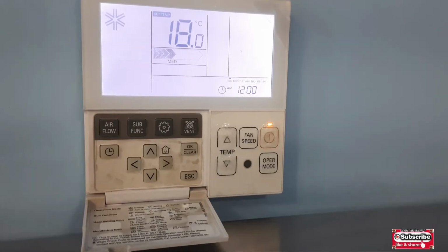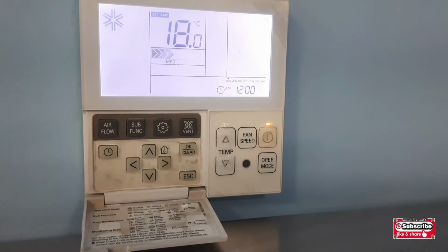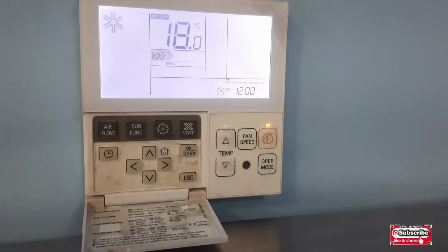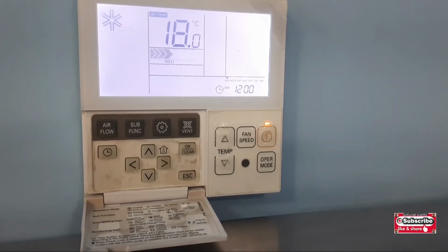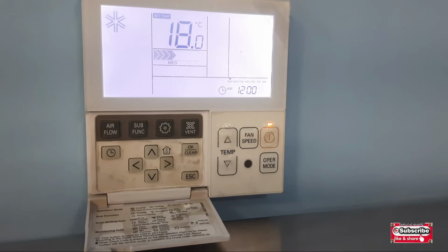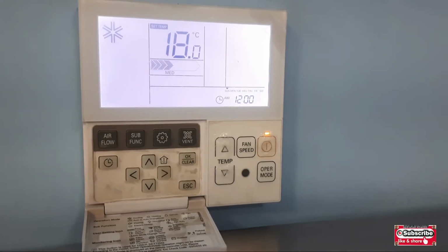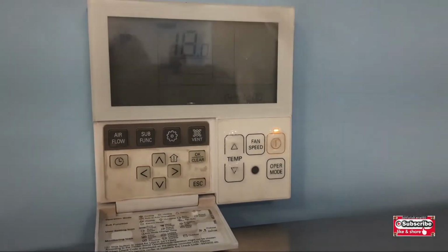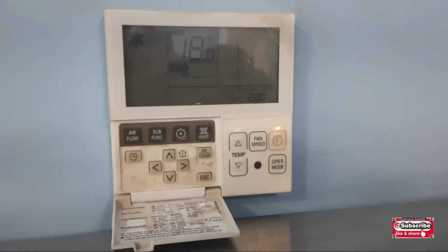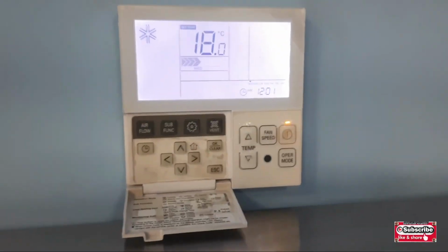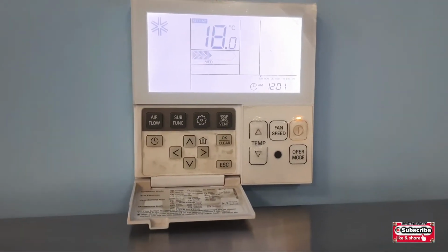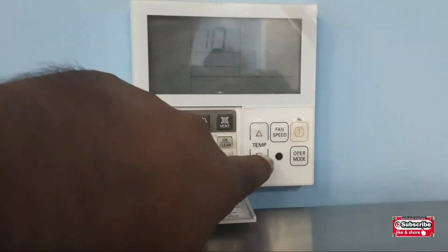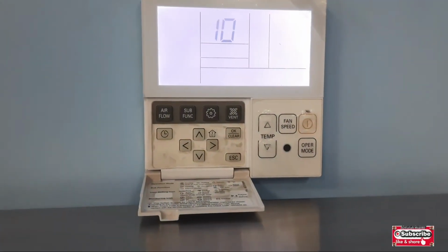So you can see practically we start the machine now. It will take almost 50 seconds. After 50 seconds the error will show in this machine, and you can see what error is coming. So let's wait for the 50 seconds. I increase the speed of my video to save your time. Let's see, when the 50 seconds will be completed, the error will show in this thermostat. Now you can see this CH10 is coming now. CH10, this came after 50 seconds.